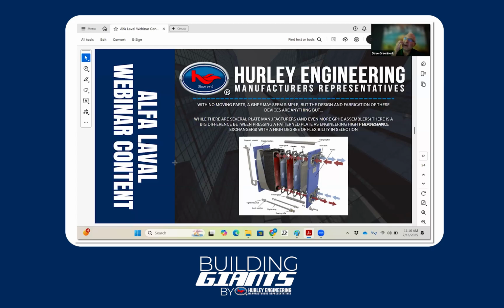That's where we have problems if they're not set up correctly. Yeah, and that frankly is I'd say the biggest problem with plate heat exchangers. They do so well in small space, lots of capacity, affordable, but that's the problem, the scale. So chilled water works really good in a clean water system. Every plate manufacturer has their criteria and their IOM. It's got to be this pH, no more silica than this, and conductivity, which implies the calcium, magnesium, and other stuff.